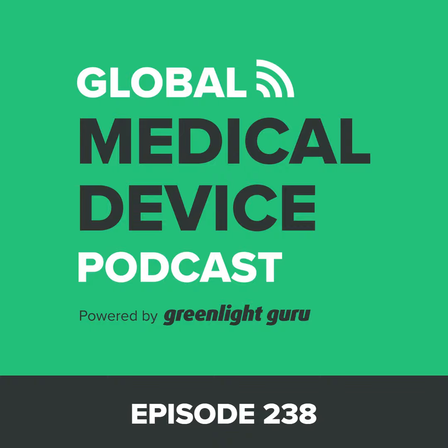The third of the four, it's intended for the purposes of supporting or providing recommendations to a healthcare professional about prevention, diagnosis, or treatment of a disease or condition. And notice that they're parsing their words very carefully, John. They're saying supporting or providing recommendations. That's short of the CFR definition of a medical device. They're not saying that they're diagnosing. They're saying that they're supporting or providing recommendations.